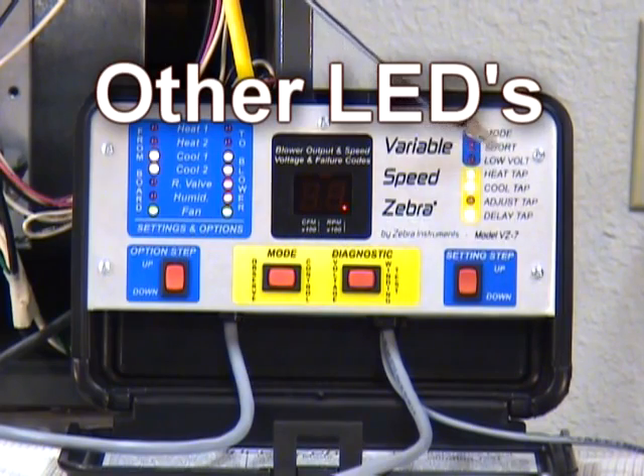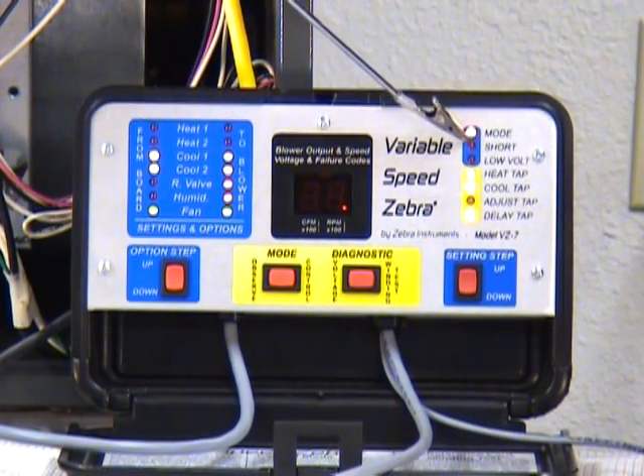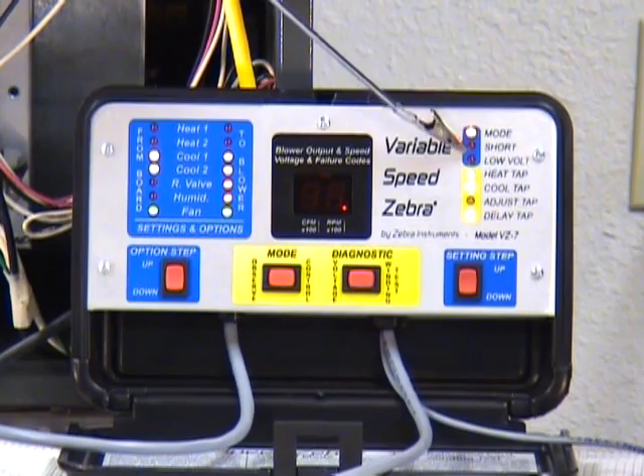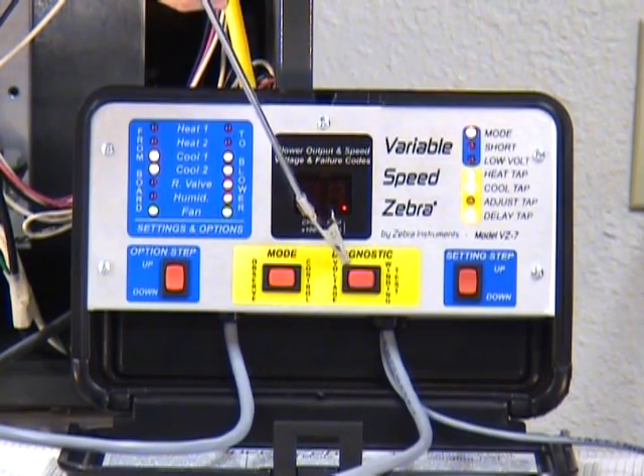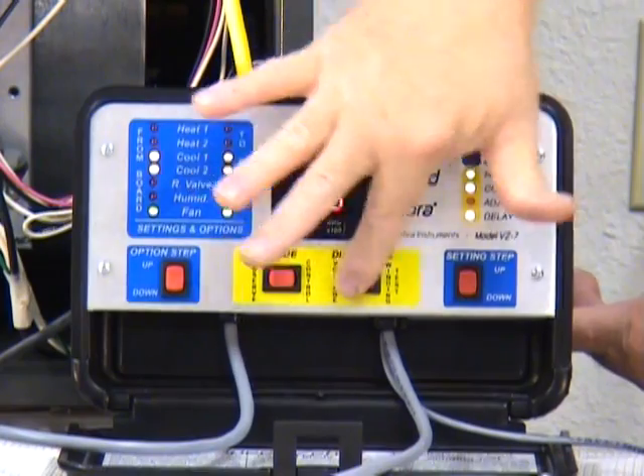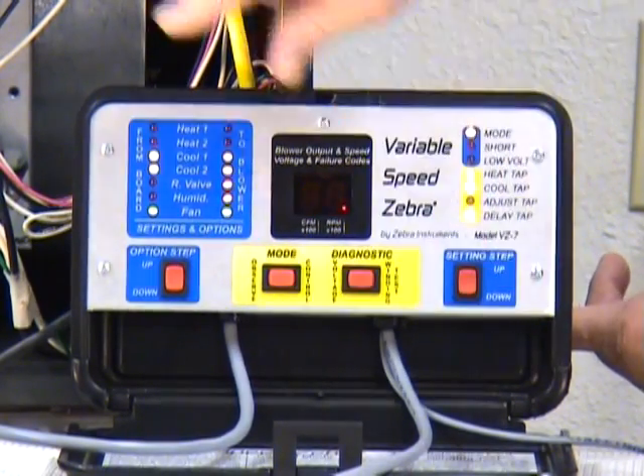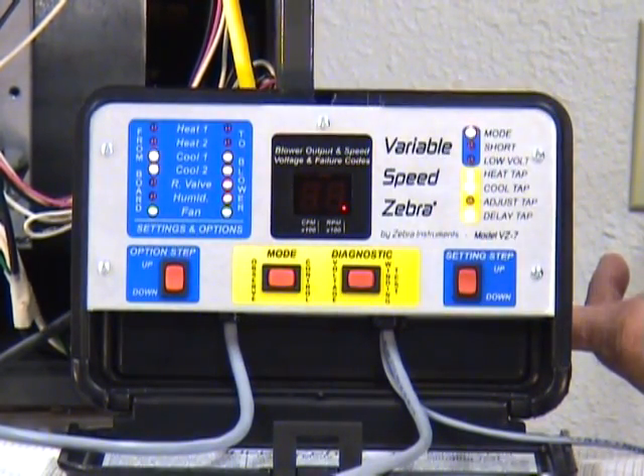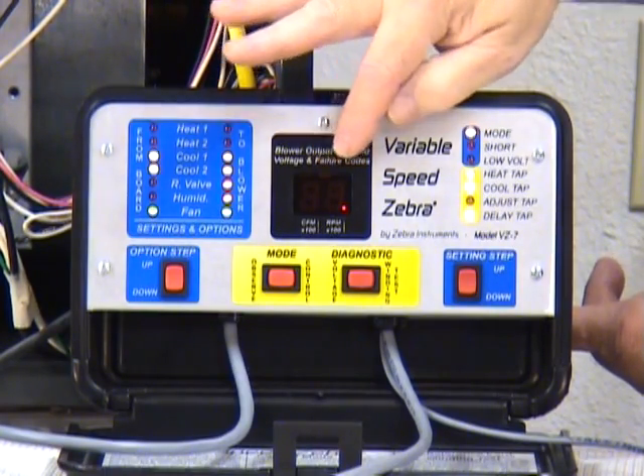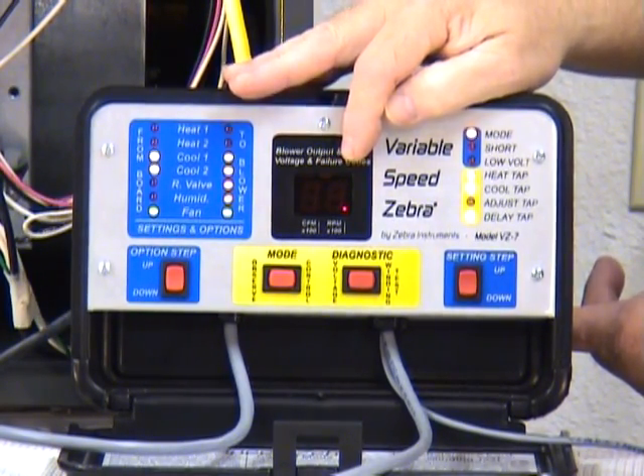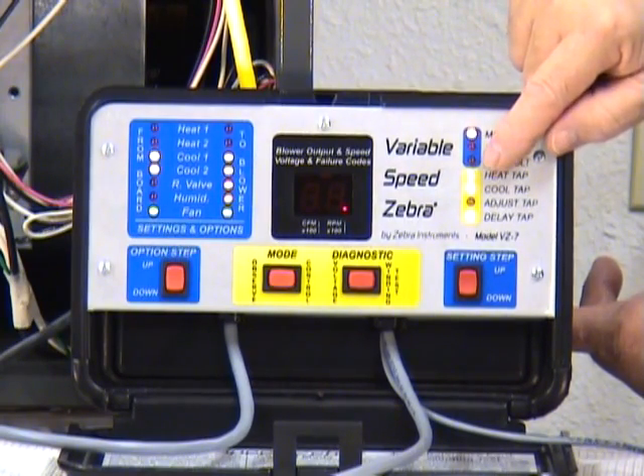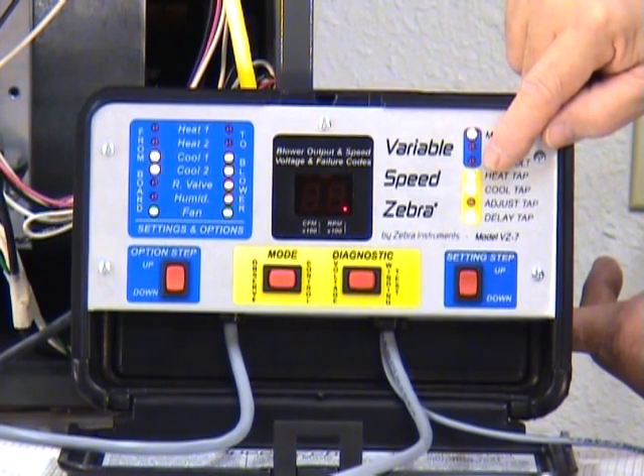There's 2 additional lights on the variable speed zebra that we ought to touch on. One's called your low volt light and the other one's called a short light. The low voltage light is hooked up to this voltage circuit. Remember when you could press this switch and get a display as to how much power on the low voltage side is actually coming into the motor circuits? This said 26. If it said less than 20.5 volts, this low volt light will be flashing continuously to let you know, don't even bother doing any of these other tests. It's just a little reminder that says, don't bother, here's your problem right here, buddy.